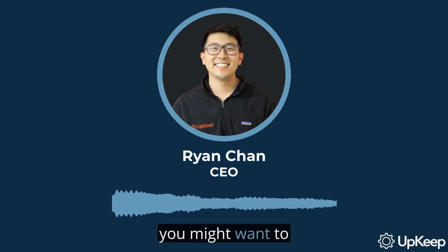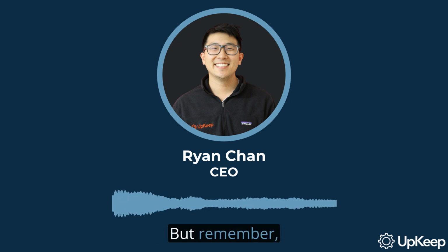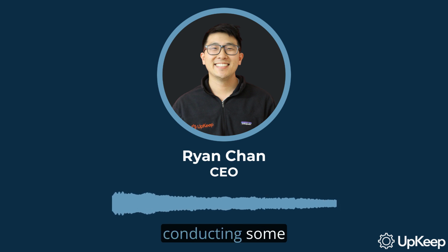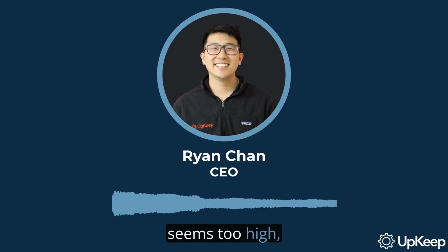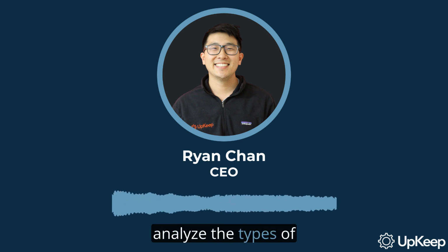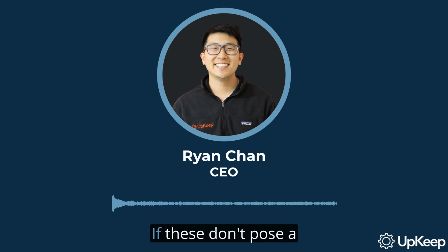If you're performing more than 6 preventive maintenance tasks for each corrective maintenance task, you might want to consider scaling back a bit. But remember, only do this after conducting some research. If your PM to CM ratio seems too high, it's advisable to analyze the types of failures you're preventing. If these don't pose a significant threat, reducing relevant PM tasks could be a good move.